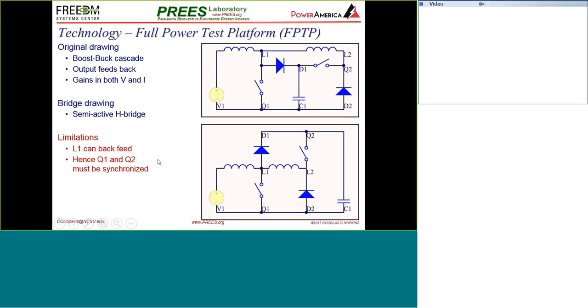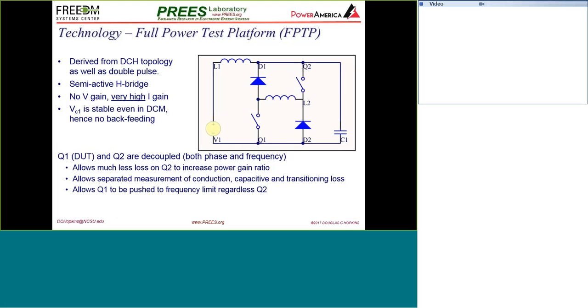Now, Bo got a hold of this and started looking at how he might want to do it, and he redrew it. The bottom one is exactly the same topology, but he said, let's do it a little differently. If I use a fixed voltage, because we're only at 10 kV and we have 10 kV power supplies in our lab, then I only need one that's high enough voltage and power to supply the system. So we're using this topology to pump energy in, and we have very, very high current gain — I think it's double digits, maybe 30 or 40 times current gain. I think the voltage is going to be fixed at whatever we put in for the power supply. So this is the topology we're building.